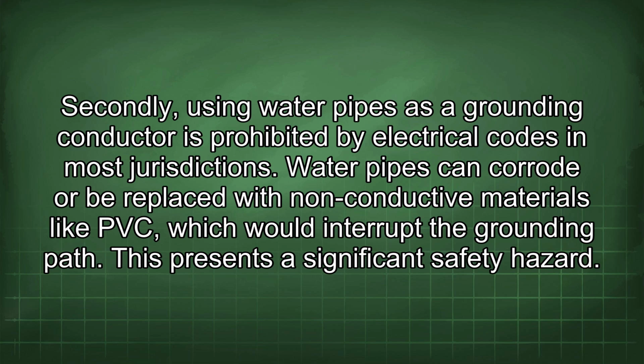Secondly, using water pipes as a grounding conductor is prohibited by electrical codes in most jurisdictions. Water pipes can corrode or be replaced with non-conductive materials like PVC, which would interrupt the grounding path. This presents a significant safety hazard.